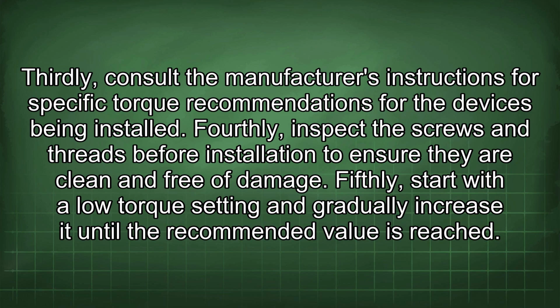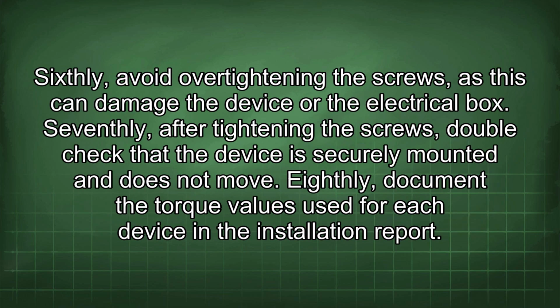Fifthly, start with a low torque setting and gradually increase it until the recommended value is reached. Sixthly, avoid over-tightening the screws, as this can damage the device or the electrical box. Seventhly, after tightening the screws, double-check that the device is securely mounted and does not move. Eighthly, document the torque values used for each device in the installation report.